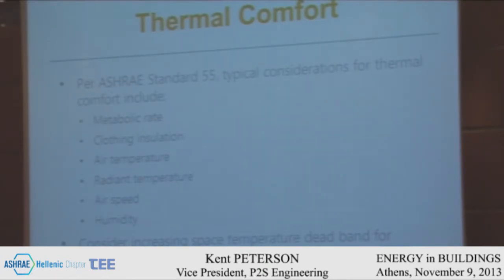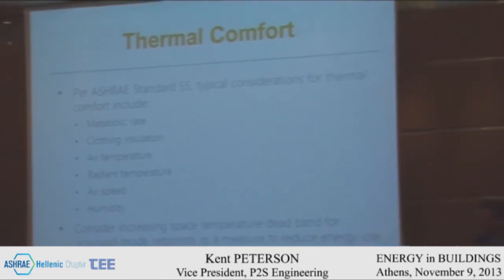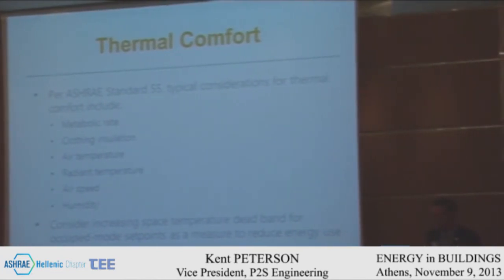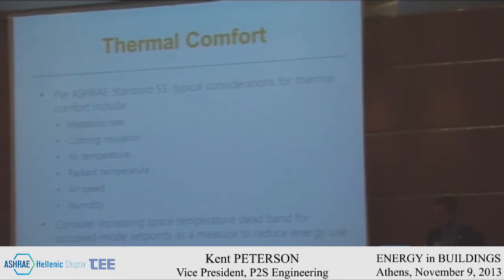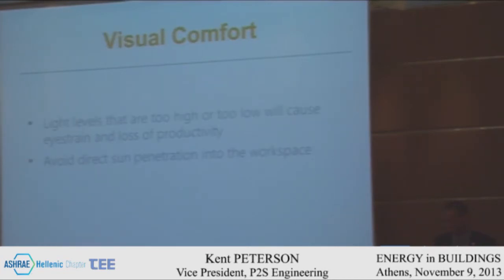Now, ASHRAE Standard 55 is our standard on thermal comfort. And this is a very good standard that's been written many years ago and continuously is updated. But this provides for thermal comfort and looking at things like metabolic rate, the clothing insulation value of what's expected inside the space, air temperature, the radiant temperature, airspeed, and humidity, and the impacts of each on each other. So if we're looking at things like passive strategies, the airspeed can have a good impact on expanding the thermal comfort range within that space. So one of the things to consider always is to increase the space temperature deadband for the occupied mode as an energy saving strategy that might be utilized to save more energy.